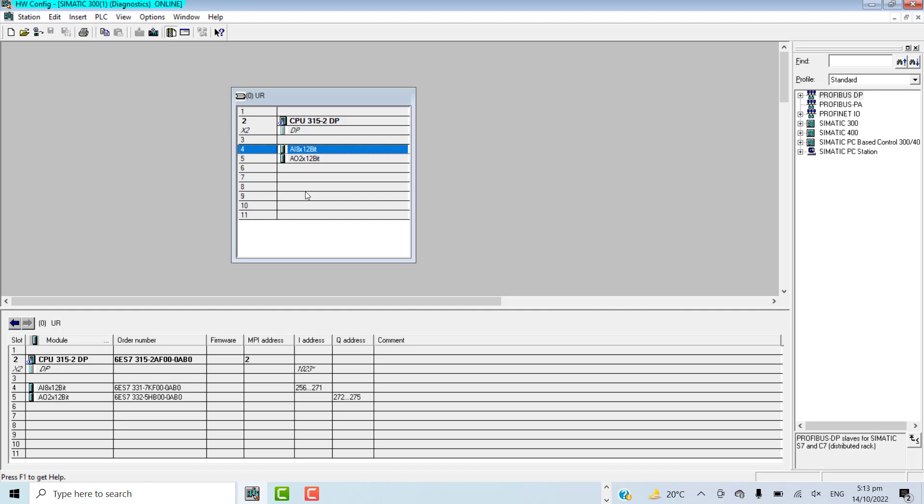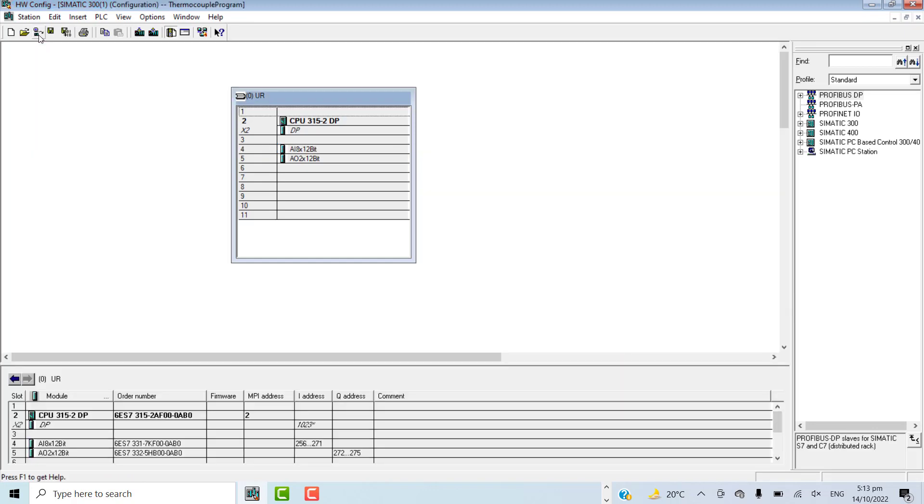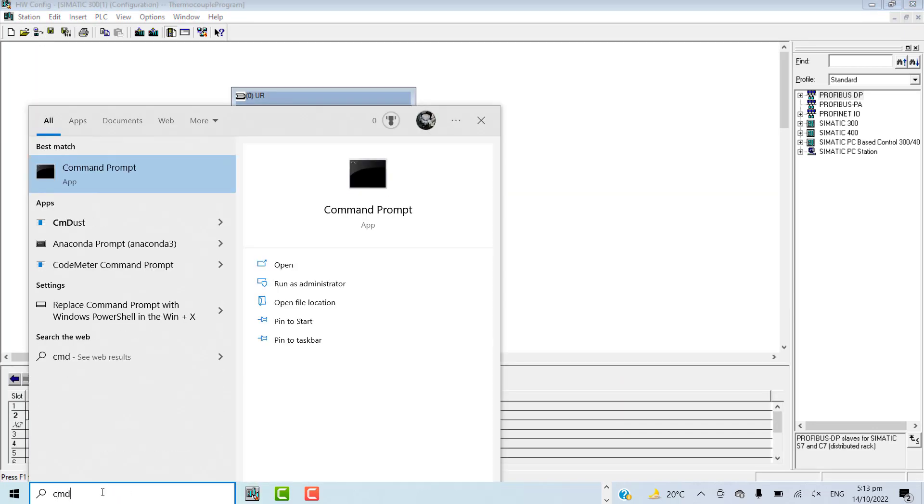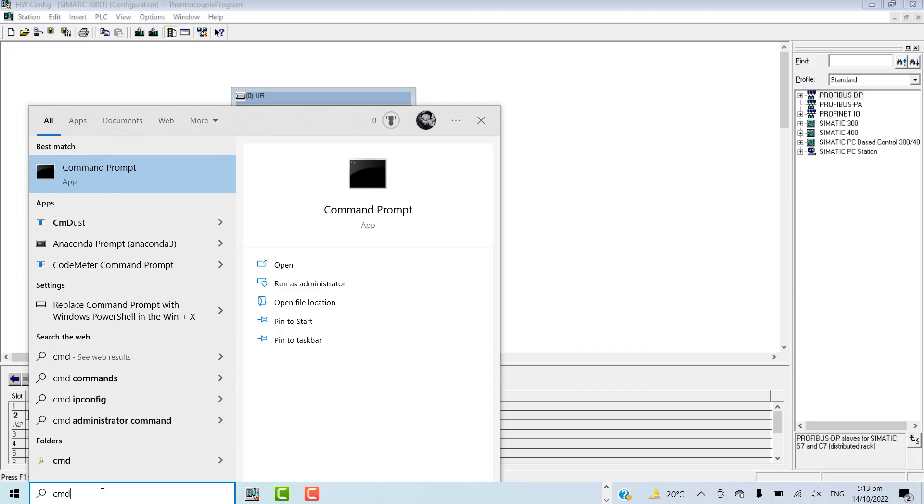The third step is to observe the status of communication between the engineering station, PG, and the CPU. If the communication is not establishing, you can check the communication status between the engineering station and PLC CPU.